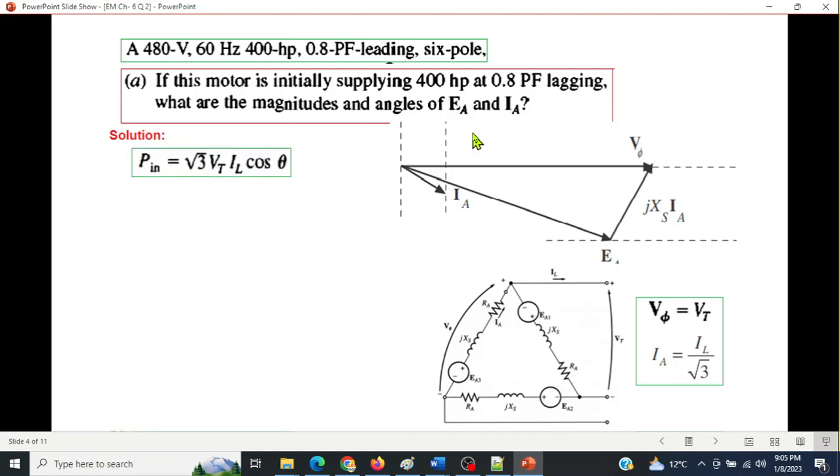So first of all, to calculate Ia, we need to know IL, the line current. Now, this is the equation for Pin, but we don't know Pin. What is given is Pout. The output horsepower is 400 horsepower. This will convert into watts. So multiply by 746. So this is the output power in kilowatt. And since there is no loss, therefore input and output will be same. So Pin will also be 298.4 kilowatt.